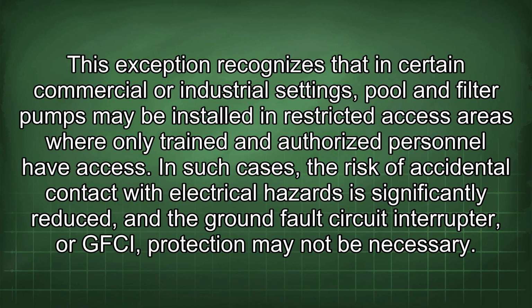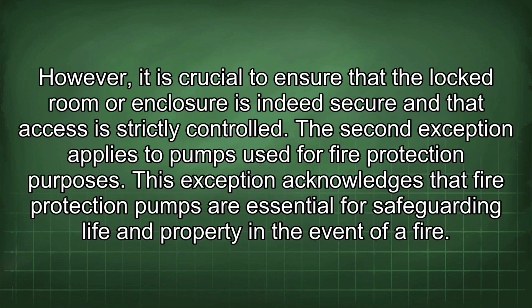In such cases, the risk of accidental contact with electrical hazards is significantly reduced, and the GFCI protection may not be necessary. However, it is crucial to ensure that the locked room or enclosure is indeed secure and that access is strictly controlled. The second exception applies to pumps used for fire protection purposes.